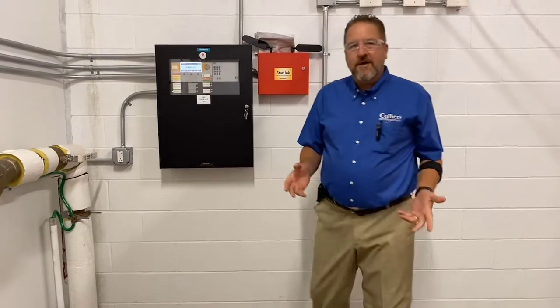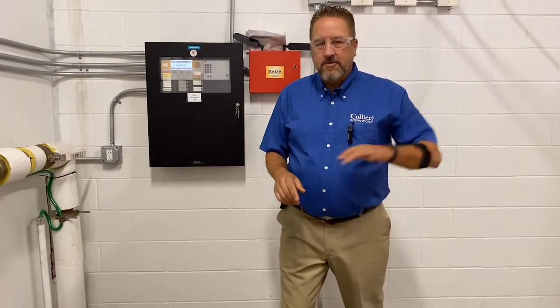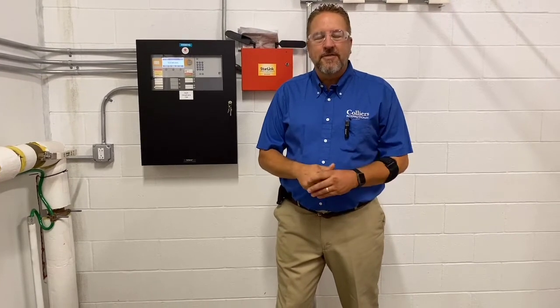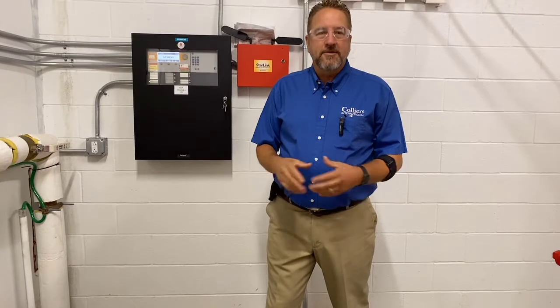You're going to call that fire monitoring company, make sure they received all those signals that you just sent them for the fire pump run and everything else. Then you're going to tell them to go ahead and place it back in their normal operating monitoring, so that way your building's protected. All right, that's pretty much it for the electric fire pump.